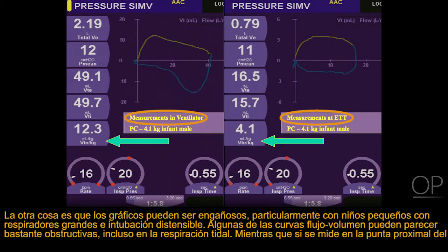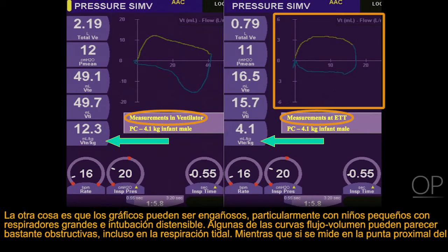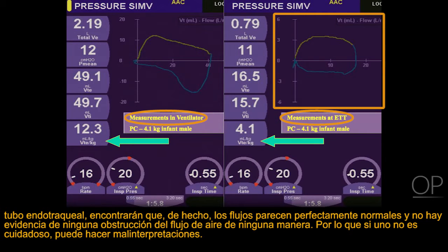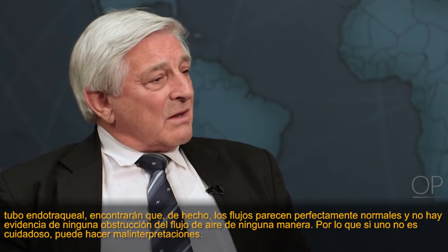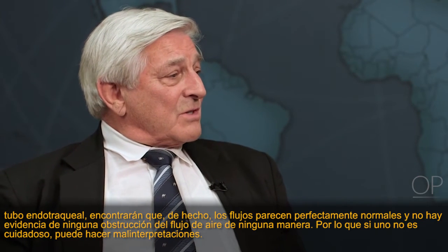The other thing is that the graphics can be misleading, particularly with small kids with big ventilators and compliant tubing. Some of the flow volume loops may look as though they're quite obstructed, even in tidal breathing, whereas if you measure it on the proximal tip of the endotracheal tube, you'll find that in fact the flows look perfectly normal and there's no evidence of any airflow obstruction whatsoever. So one can make misinterpretations if one is not careful.